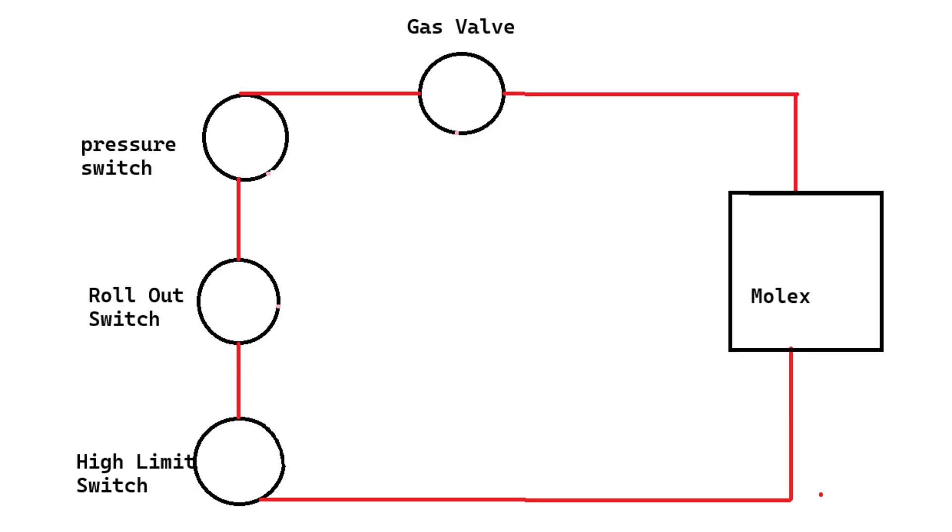So this Molex wiring arrangement is no different than if you had just one wire coming out of the Molex, going through the high limit switches, then through the flame rollout switches, then through the pressure switch, and then finally to the gas valve. With no other wires coming back outside of the common from the gas valve itself. It still has to travel through each component one by one, and there are no other paths.